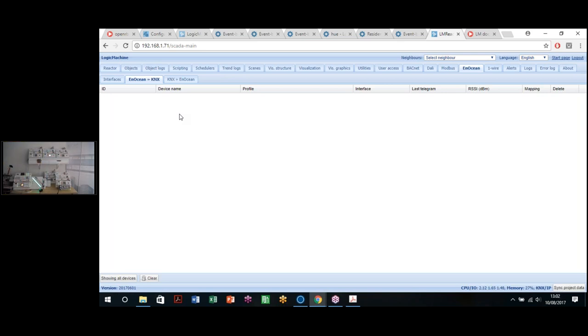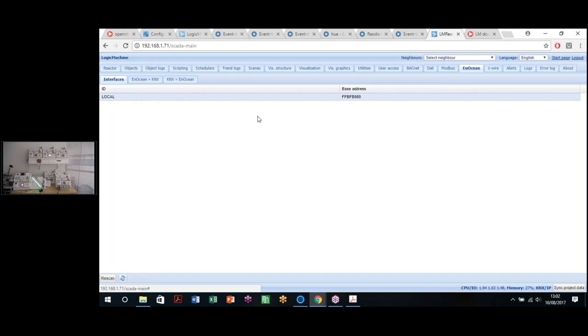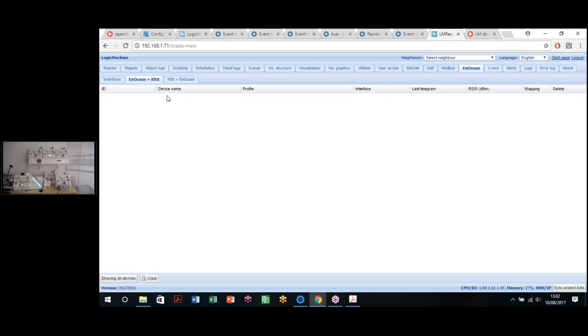And in the EnOcean screen, we can see that we have three different tabs. We have the interfaces tab, where we will see the interfaces installed in the Logic Machine, and we have the EnOcean to KNX. So these are for input devices, and then we have the KNX to EnOcean configuration. In this case, we're using some push buttons, so it's from EnOcean to the Logic Machine.